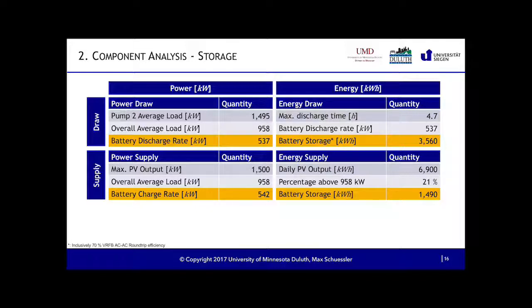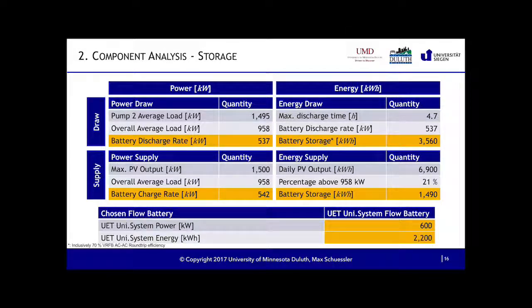And when I look at the supply side from the PV, already 1.5 megawatt hours of storage would be sufficient. But the problem is, I need one battery and not two batteries to meet my needs. So I looked at what is on the market, and I showed you already the picture of the UE Technologies battery, and it fits quite well, with a system power rating of 600 kW and an energy rating of 2.2 megawatt hours. I took this battery, which is really on the market and we could actually install, and looked at how we could operate it to get the most out of the system.